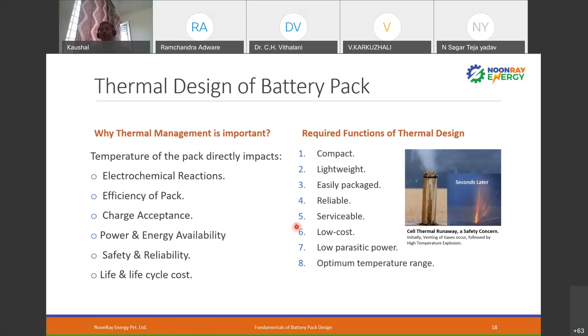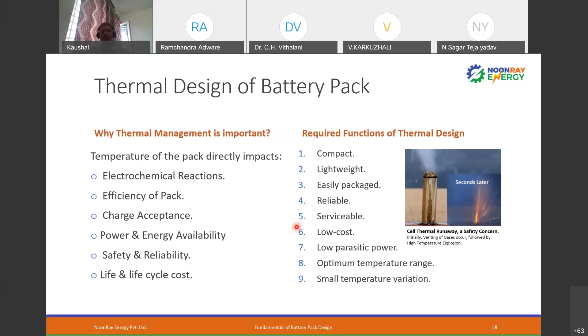A small temperature variation within the pack. When I say within the pack, I mean from the first cell to the last cell, as in the picture I showed you earlier. I should not have a huge temperature gradient. It should be minimum. If my first cell is at 35 degrees, my last cell in that pack should be at 35, and the center cell should also be at 35. However, at the center cell you have very little space to dissipate heat. So you need to give more cooling capacity at the center location. The temperature variation within the cells in the pack should be minimum.